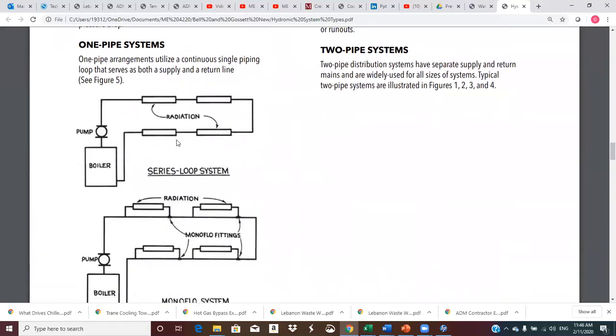Okay. We have situations where we can do one pipe systems, where we come out, we go through radiation, a coil, something like that. This could be a baseboard radiator. And what happens is, as we take heat out of this thing, the temperature simply falls. We might be 200 here, maybe 190 here, 180, 170, 160 before it goes back to the boiler. And of course, the sizing of the units has to be taken into consideration to get the appropriate amount of heat out. So that's a series loop.